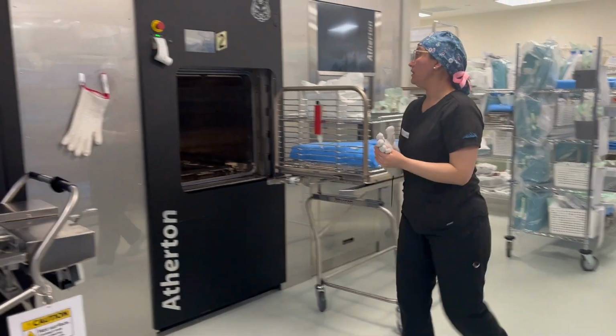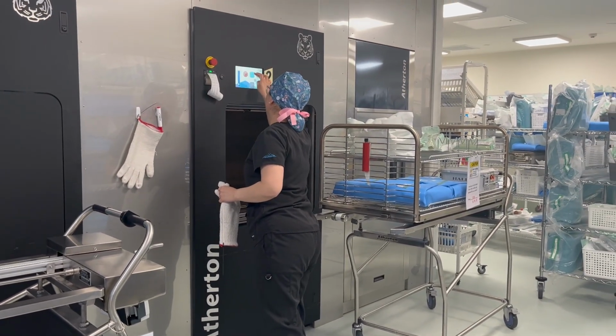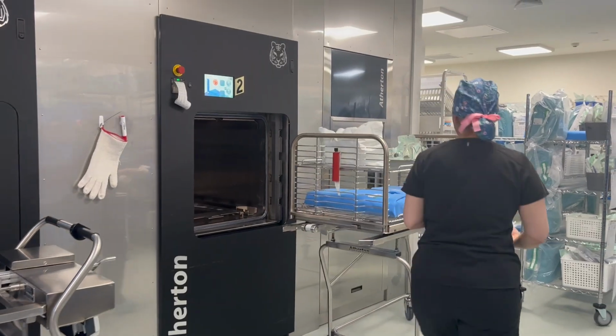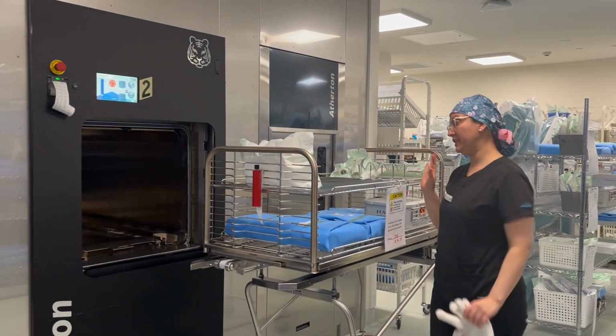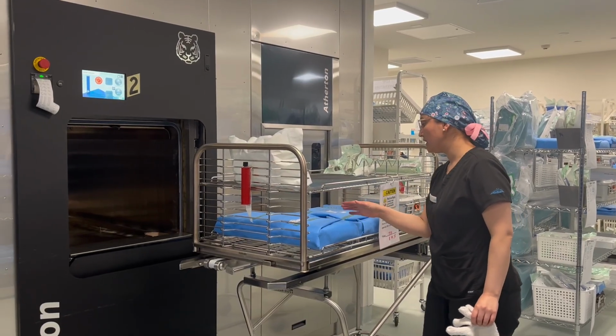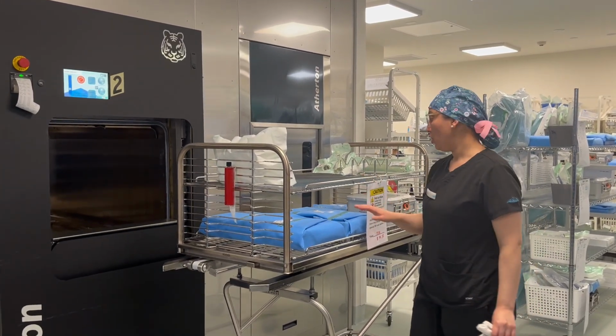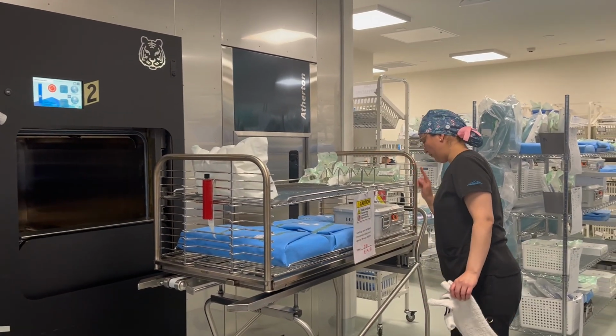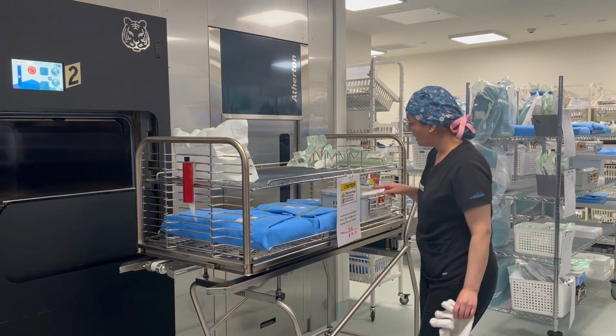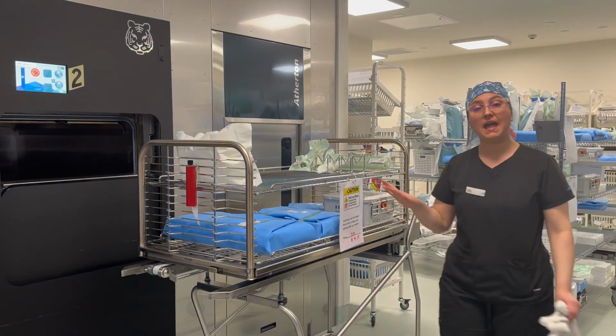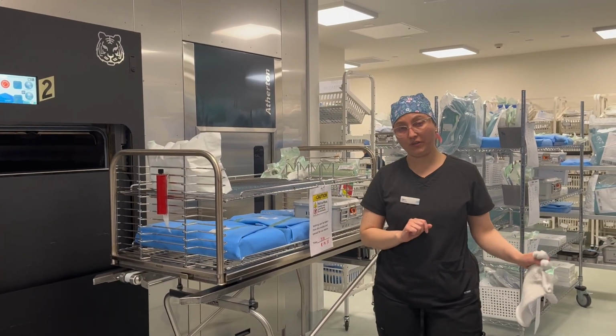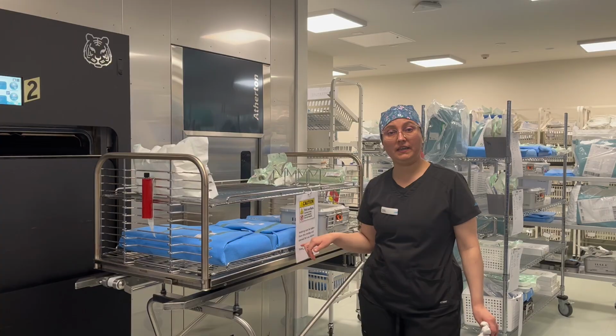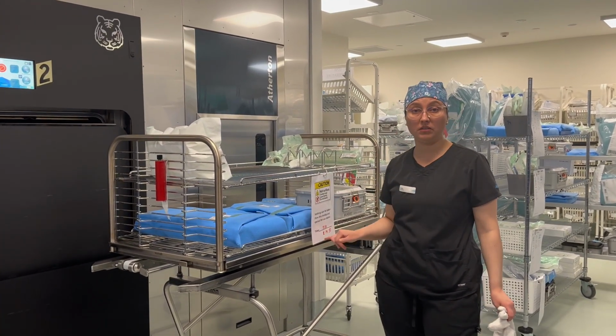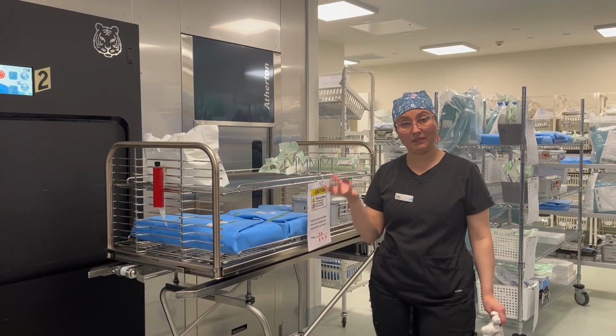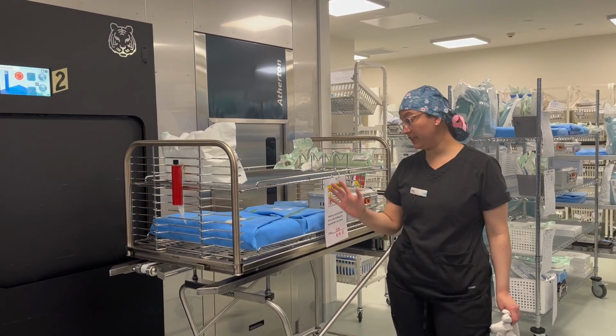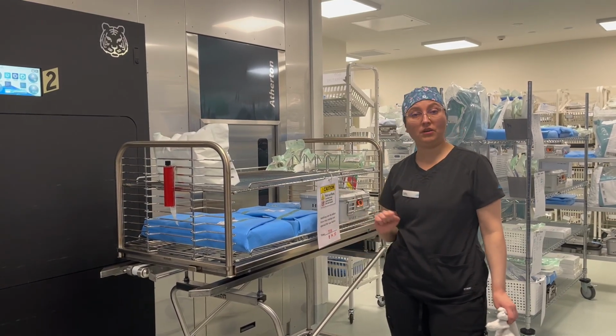So I'm going to close the door of the autoclave, and I'm going to check now, without touching anything yet, if the batch labels are attached and there's no sign of wet packages or moisture. Everything looks fine. The indicators change color and the batch label. Now we have to wait for at least an hour before the items are stored. If someone takes one of the sets before the set is cooled down, it can create wet packages, condensation, or moisture. For that reason we have to wait for at least an hour before we touch any of the sets.